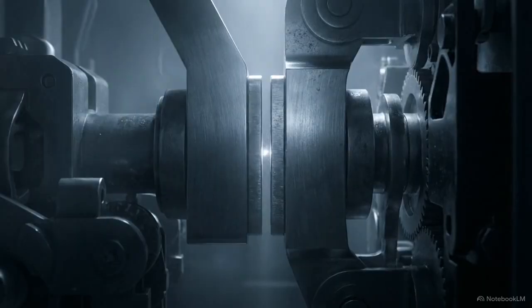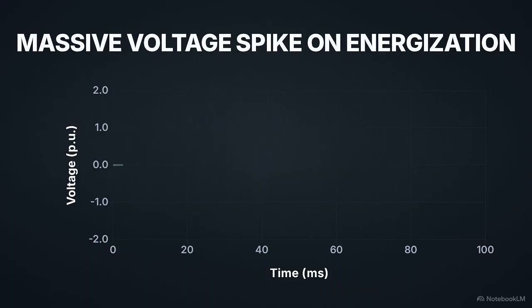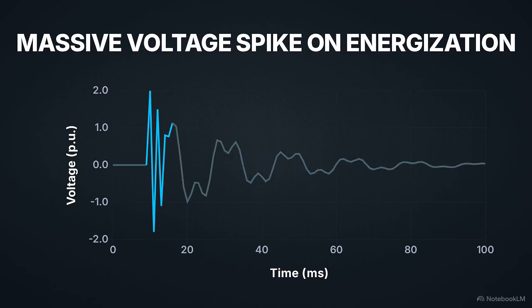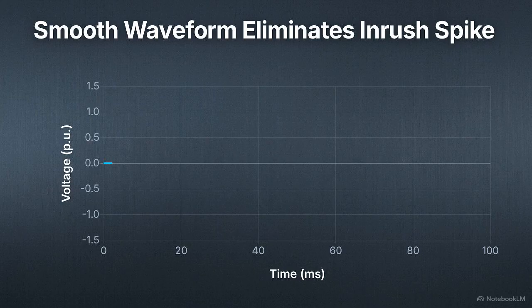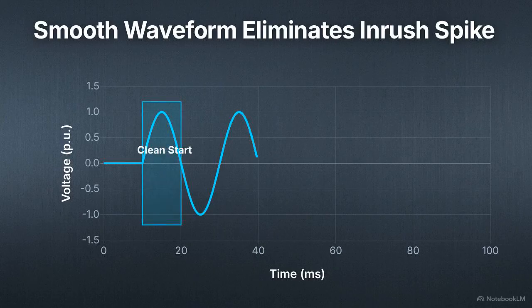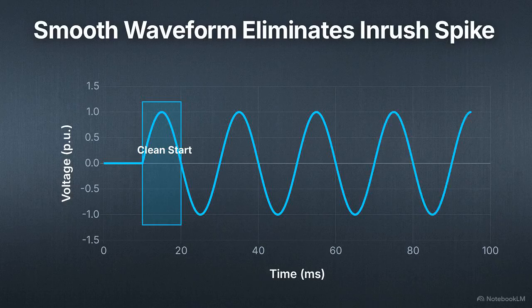a second. This oscilloscope capture shows the chaotic reality of a standard, uncontrolled grid switch. That massive, jagged spike on the left is the erratic voltage transient ripping through the system. By contrast, this capture shows the exact same equipment energized using a POW smart controller calculating residual flux. The spike is gone, replaced instantly by a smooth, stable sine wave.